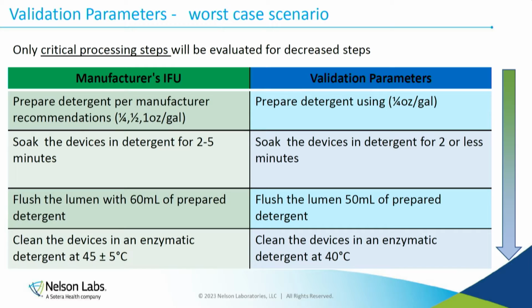This shows what your IFU is and what the testing lab did, right? It says per label claims, we take it to the lowest. It says soak for 2 to 5 minutes, we take it to the lowest. We'll do 2 minutes. We're not going to do 5 and we're not going to do 3. We're going to do 2 minutes, and things like that. Processing steps that will impact the endpoint are the steps that we will reduce. Now, if you reduce everything, you're going to fail. So we have to be very smart about which parts of the IFU we are reducing.